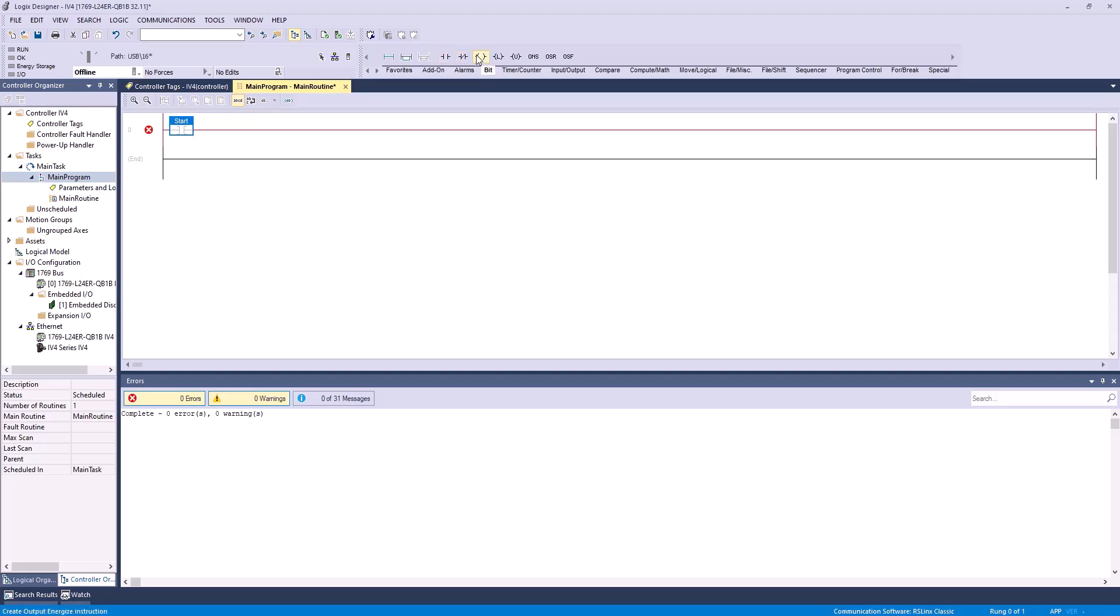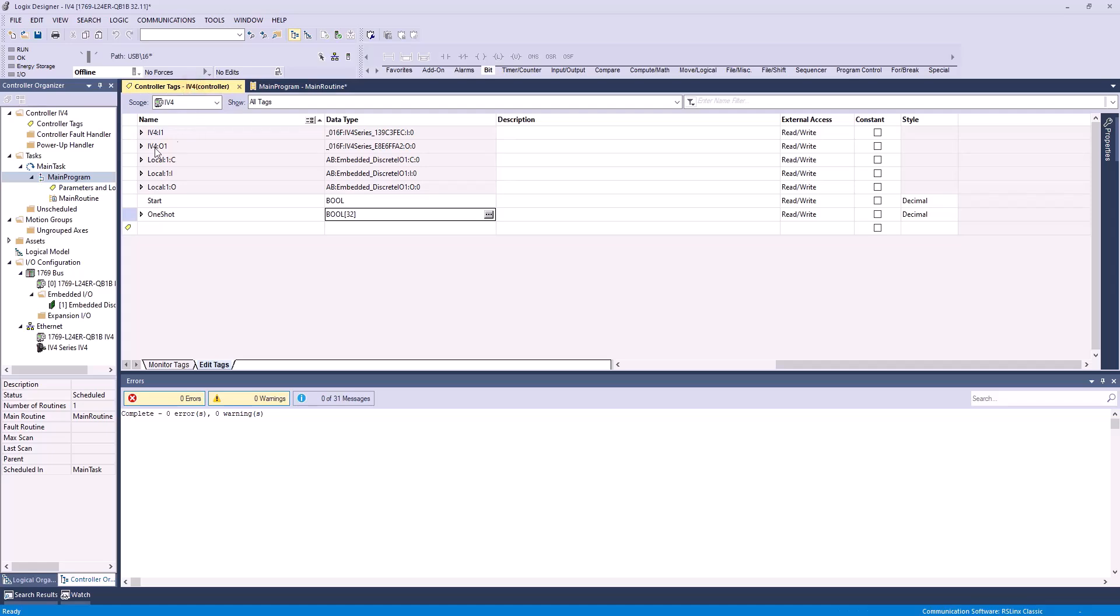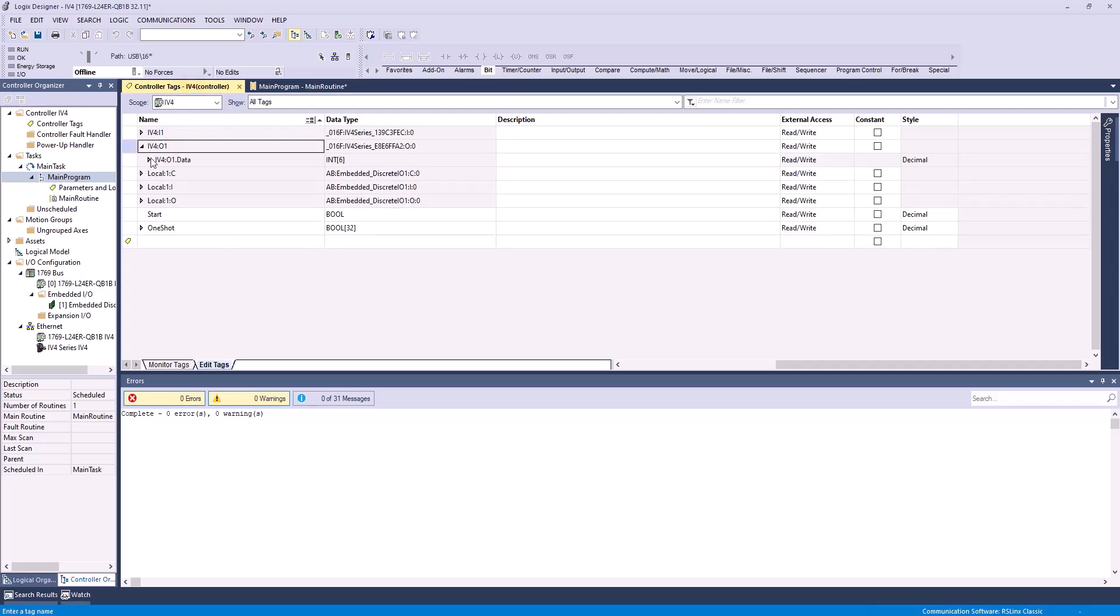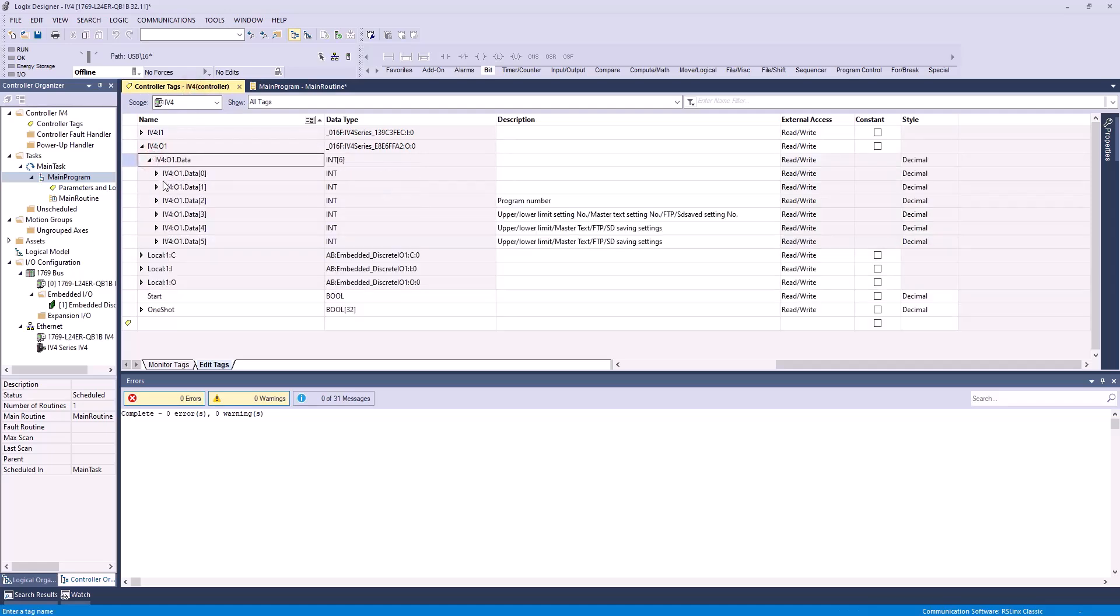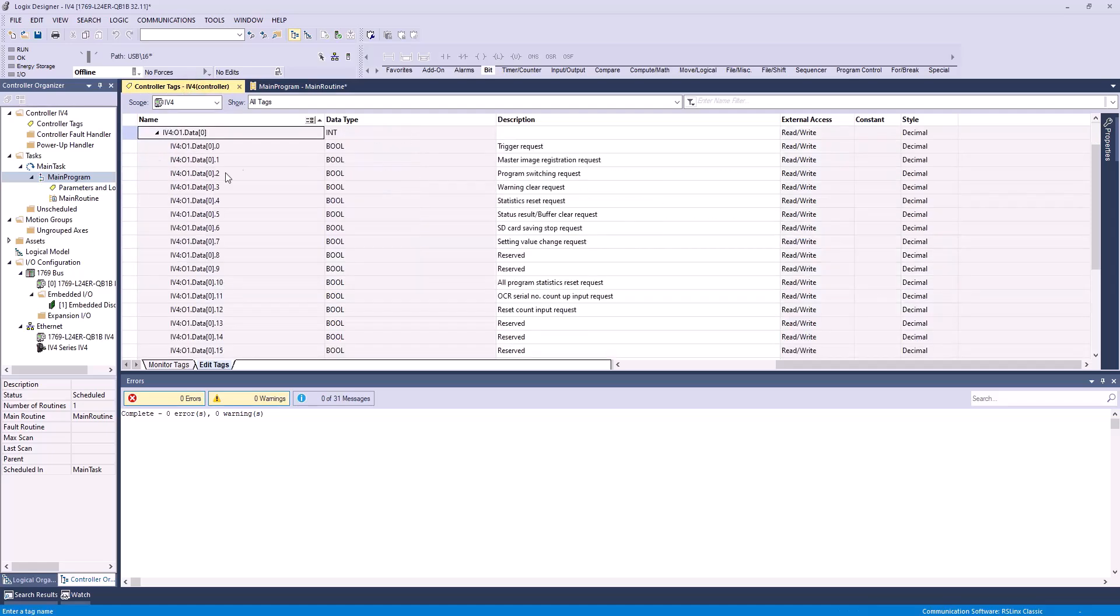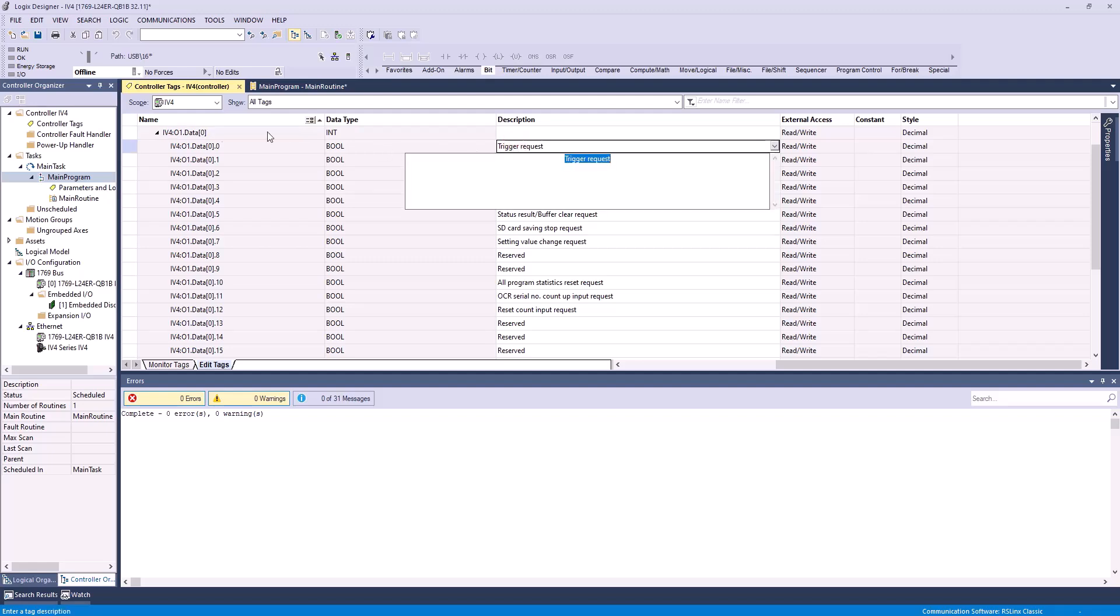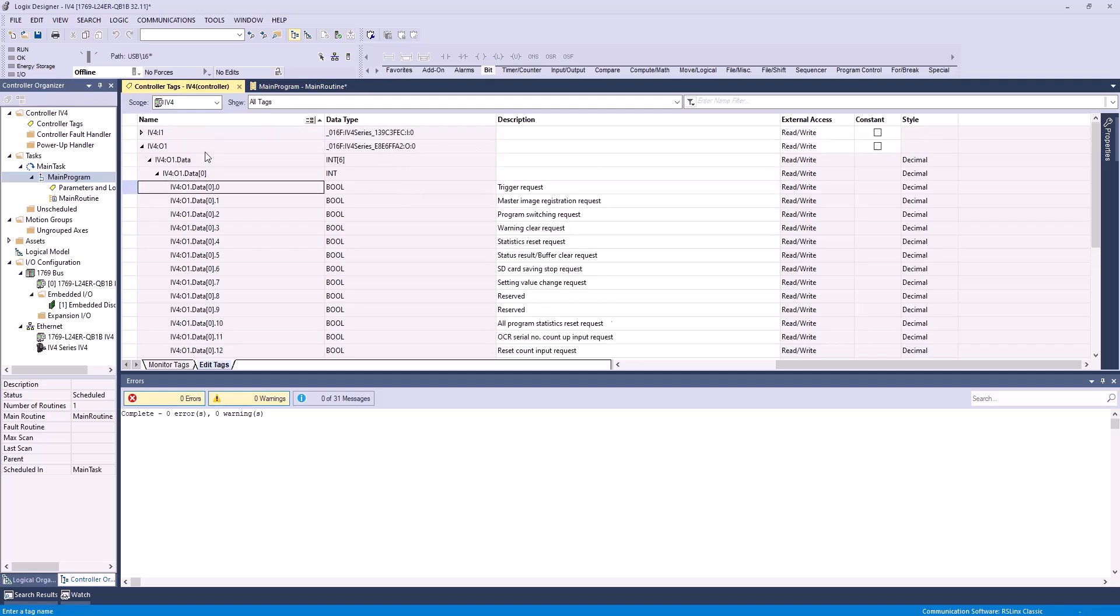Next, we'll need a coil, because when we turn this on, toggle that bit on, we want it to activate something. In this case, we want it to activate our trigger request. Now, you can find the trigger request. It'll always be in output 0.0, and it's labeled there. This information can be found in the IV4 user's manual, or just in your tags here when you load it in.